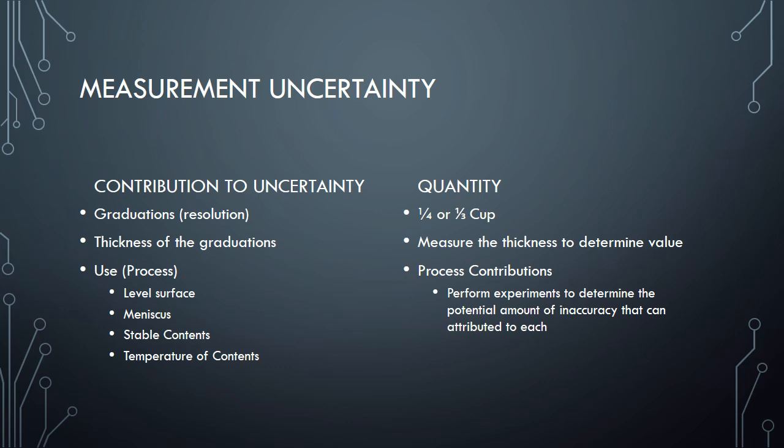When we look at measurement uncertainties, there's these contributions and then there's a quantity associated with that contribution. When we looked at the potential measurement issues with using our measuring cup - like the graduation, the resolution, the distance between the graduations, the thickness of those graduations, and the actual use of the measuring cup itself - we can then go and try to identify some quantities to associate with that. Because those quantities that associate with that will then drive what the value of our measurement uncertainty actually is. In that case, we look at our graduations and they're either a quarter or a third of a cup per graduation. We wanted to figure out what the thickness of those graduations was, so we would measure the actual thickness and determine a volume to associate with the thickness of that line.